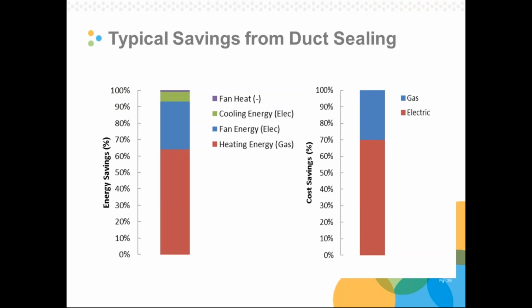However, if we look at cost savings, the picture changes a bit, and this is solely due to the difference in cost of gas and electricity. We find that when we add up fan energy and cooling energy, the cost savings on that is about 70% of our total. So 70% of our cost savings are coming from electric, and the remainder, about 30%, is due to the gas energy we use for heating.